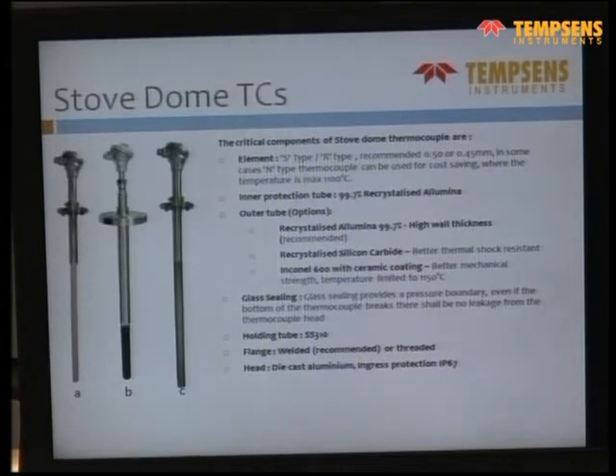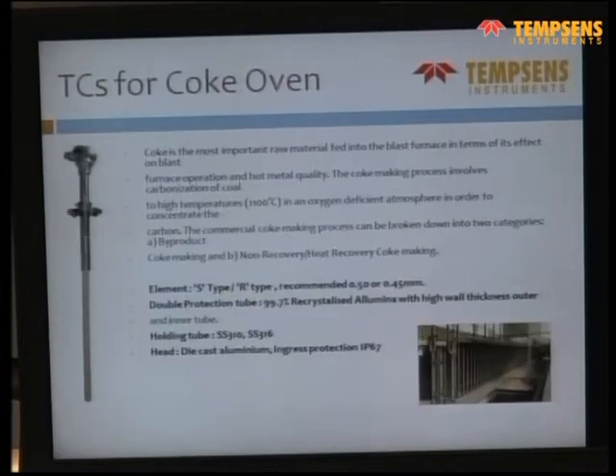And in this case, just below the head, we use a ceramic to metal seal. So even in case the thermocouple fails, the blast would not come out from the head. This is the kind of solution we are offering, so it could be applicable for some of your cases also. We are using glass sealing so that even if the thermowell breaks, the blast is not going to come out from the head. So this is for the stove dome.